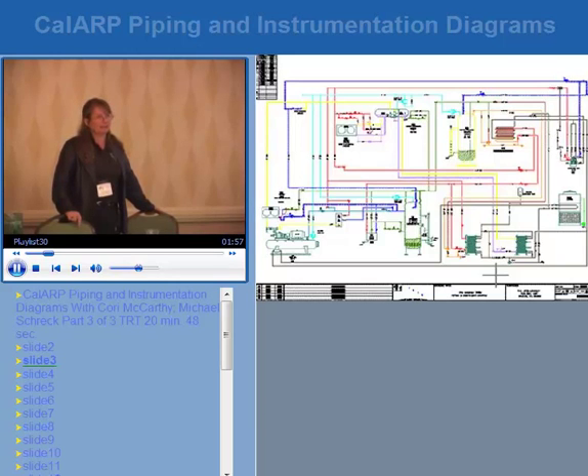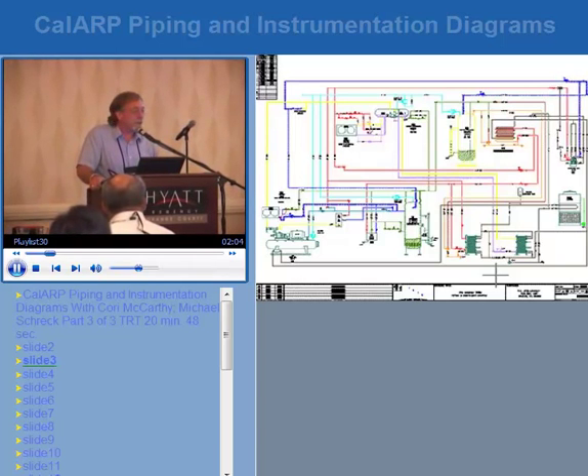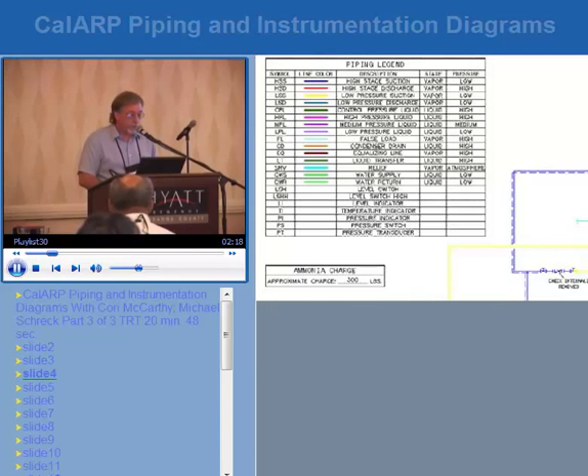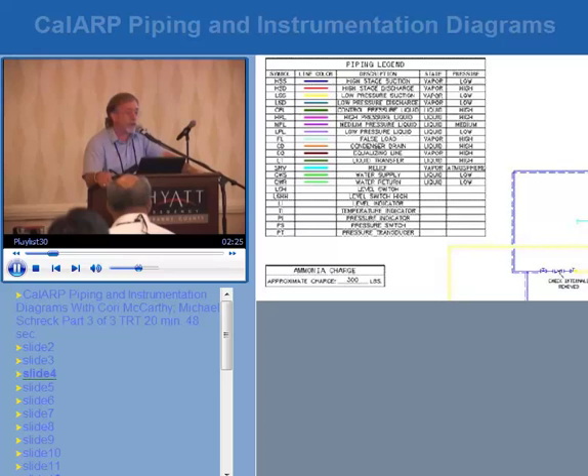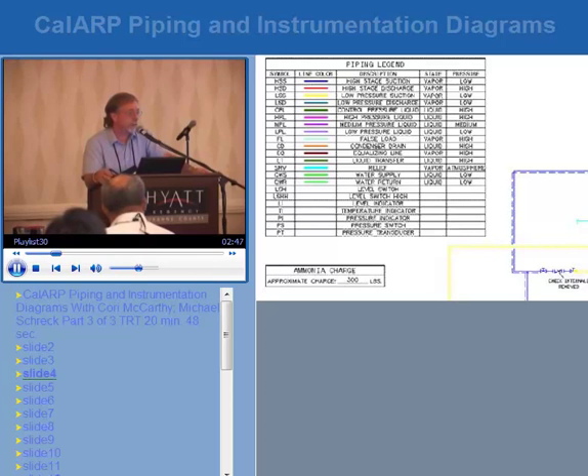Looking at a very simple P&ID of a two-stage system used for cold rooms at minus 20 degrees or lower — it's the start of a P&ID but it is not complete. Commonly, if P&IDs are color-coded, the first thing you'll see is a piping and control legend showing color codes — high-stage suction, high-stage discharge — and the three or four letters used on the pipe label to identify where that ammonia comes from or where it goes. That's a process of reading P&IDs, going through training specific to the system, and understanding the acronyms.